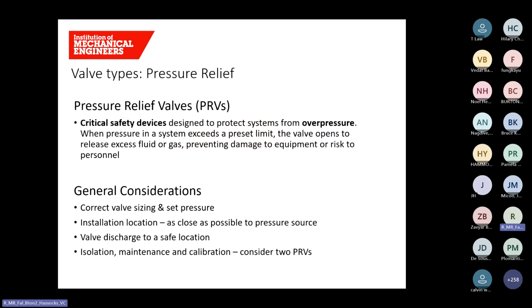This section covers pressure relief valves. Terrible jokes aside, pressure relief valves are critical safety devices designed to protect systems from overpressure. When pressure in a system exceeds a preset limit, the valve opens to release excess fluid or gas. This prevents damage to equipment or risk to personnel.